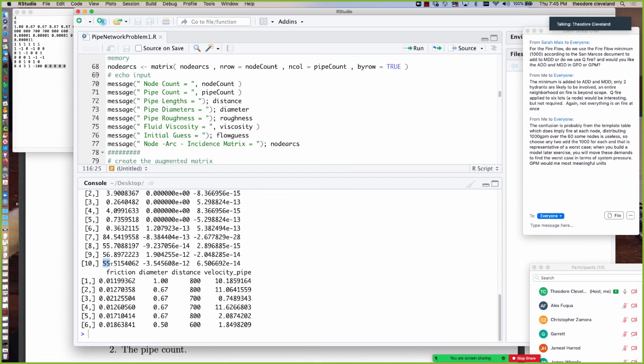4 was the rightmost node, so it makes sense that it's the smallest. And what we see here is actually considerable head loss going from the fixed grade node into node 1. There's 16 feet of head loss in that first pipe. And then there's another almost 30 feet of head loss getting to the endmost node. So if the node elevations were input, then we can recover the pressure heads and find out if we have pressure at the right PSI.